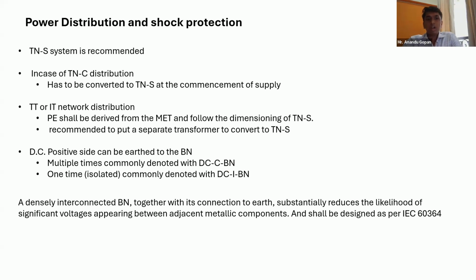One more thing is, if you have multiple connected DC, DCC and isolated DC, how are you supposed to choose between these two things? You see, when you have a multiple connected DC on your positive side, you're having multiple connections to earth. This will result in, you can use this cross section for higher current, and the temperature will be less, and the voltage drop will also be reduced because the mutual impedances are low.